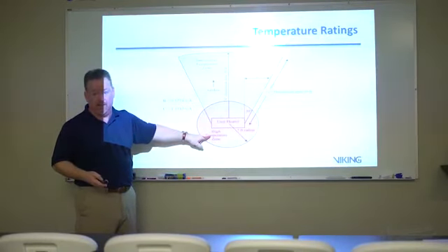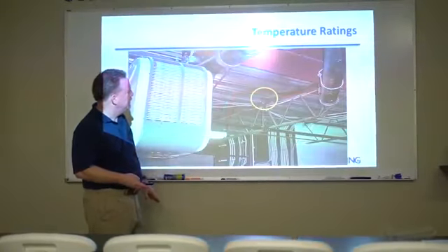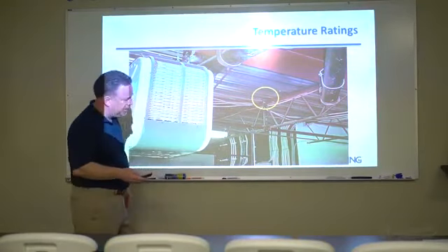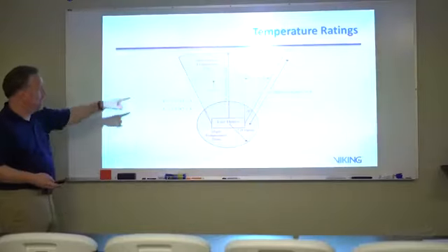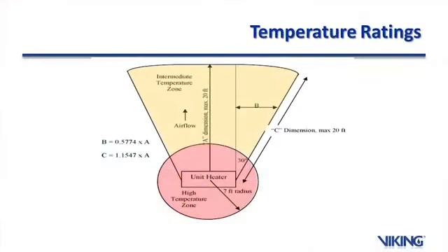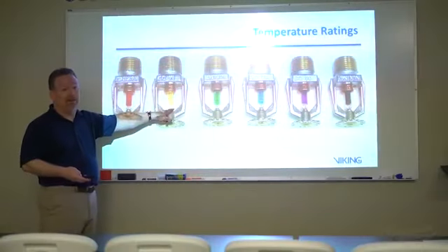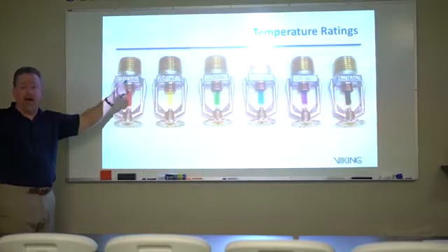Now, out in the direction of flow, so if I go back to this one here, which is in the direction of flow with that heater, I'm going to have an intermediate temperature sprinkler. So if you go back there, what you should be seeing is the color coding should change in that direct area. So yes, it's where the flow is coming out and how close it is.